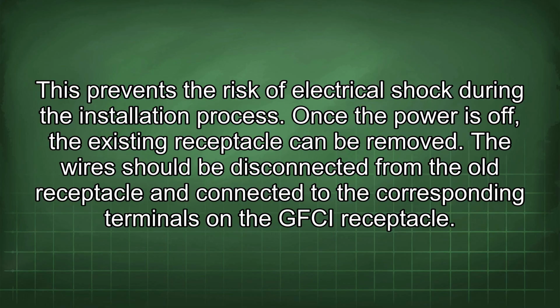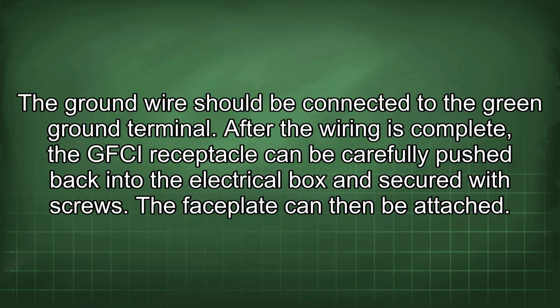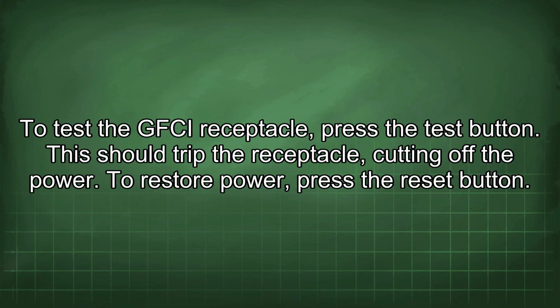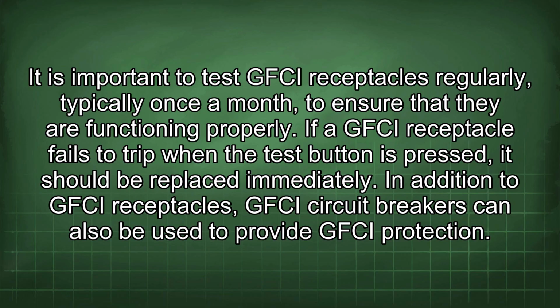Once the power is off, the existing receptacle can be removed. The wires should be disconnected from the old receptacle and connected to the corresponding terminals on the GFCI receptacle. The ground wire should be connected to the green ground terminal. After the wiring is complete, the GFCI receptacle can be carefully pushed back into the electrical box and secured with screws. The faceplate can then be attached. To test the GFCI receptacle, press the test button. This should trip the receptacle, cutting off the power. To restore power, press the reset button. It is important to test GFCI receptacles regularly, typically once a month, to ensure that they are functioning properly. If a GFCI receptacle fails to trip when the test button is pressed, it should be replaced immediately.